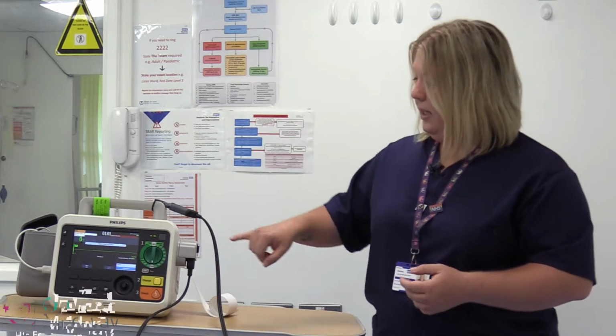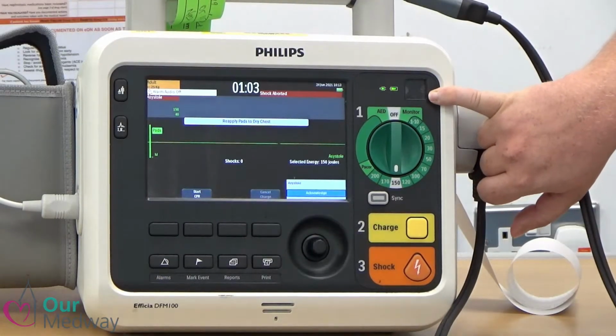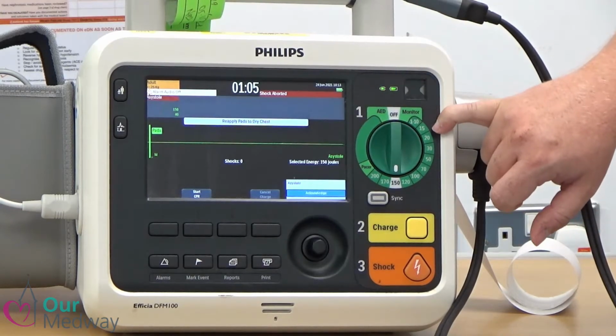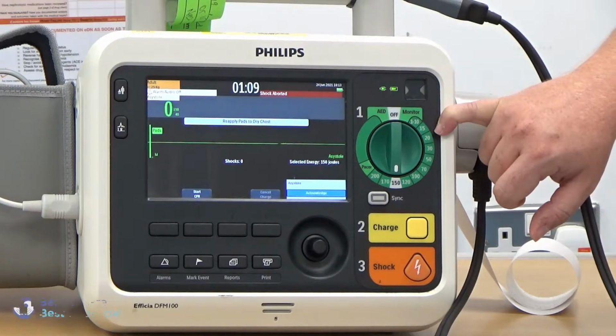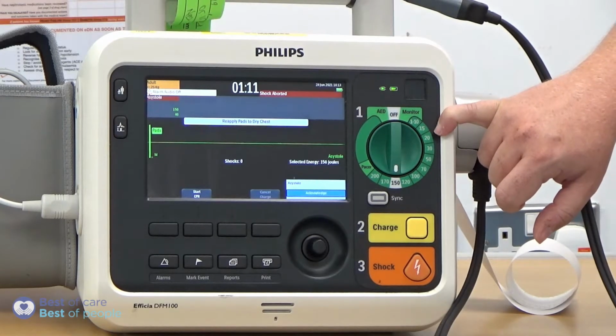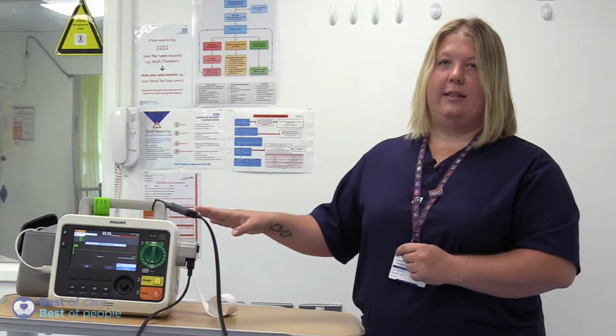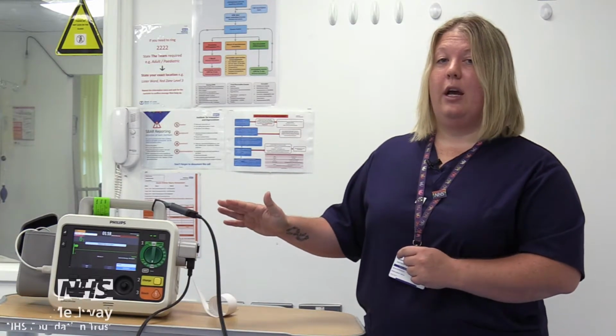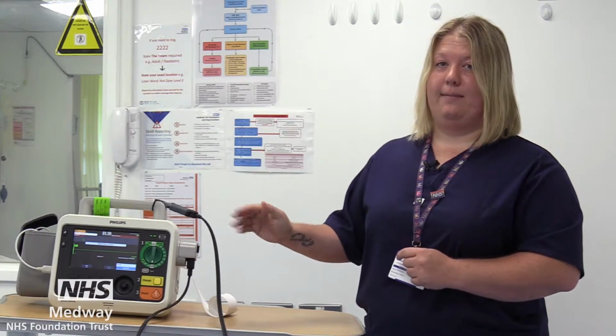The other way to know that this defib is ready is to check this top window. If you have a flashing, what looks like an egg timer in that top window, again, this defib is functional and safe for use. If you see a red cross or X in this top window, this defib is not safe for use and you need to do a test on it.